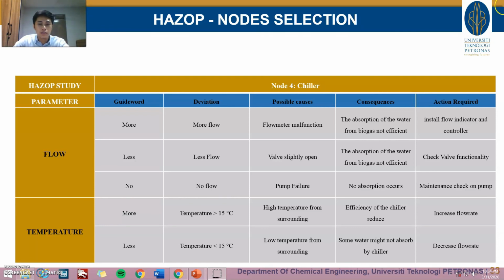For temperature above 15 degrees Celsius, high temperature of the surroundings is the cause. Consequence, efficiency of the chiller is reduced. Action required, increase flow rate. Temperature below 15 degrees Celsius, possible cause is the temperature from the surroundings. Consequence, some water might not be absorbed by the chiller, and action required is to decrease flow rate.